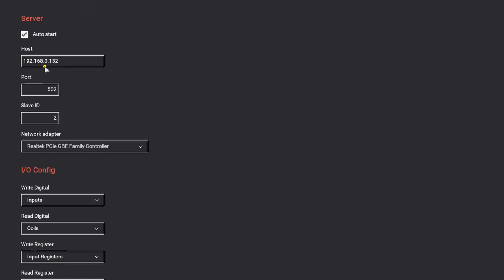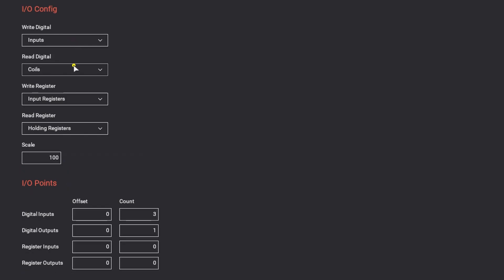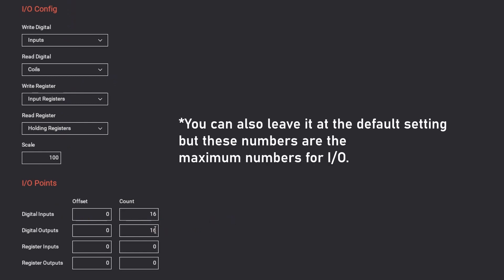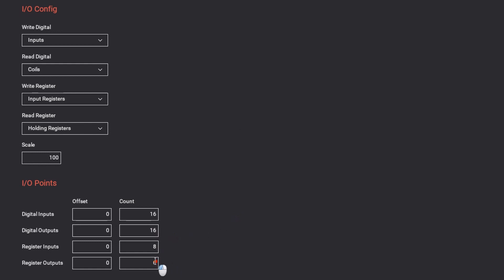So host is by default this IP address, port 502, slave ID 255. This is normally for everyone the same, and then we have 16 digital inputs, 16 digital outputs, 8 register inputs, and 8 register outputs. The registers, inputs, and outputs are actually analog inputs and analog outputs.